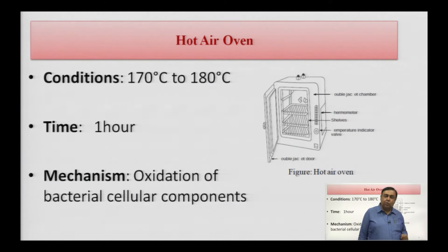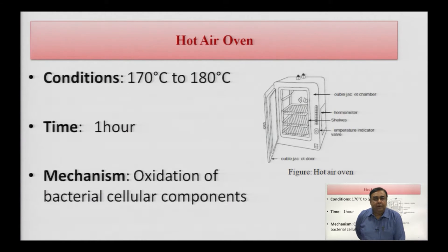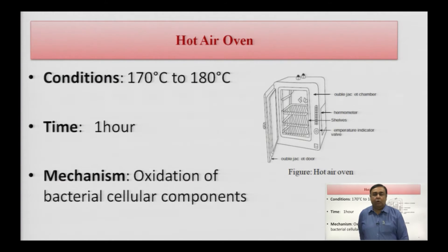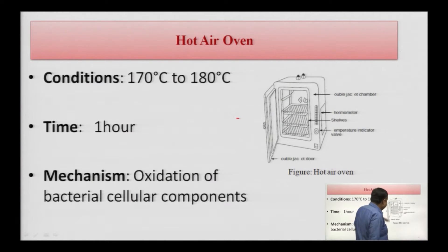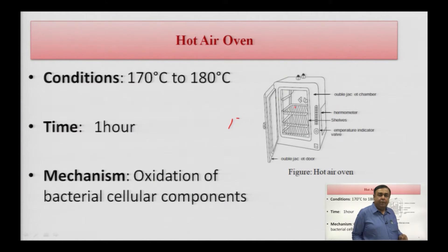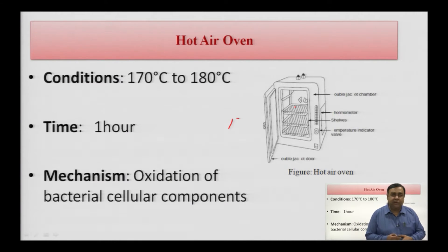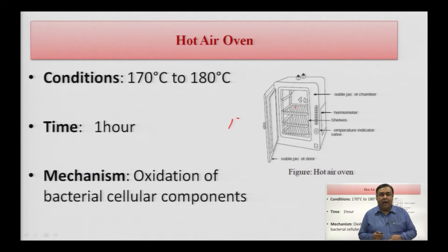The instrument commonly used in industries for dry heat sterilization is the hot air oven. The hot air oven is basically a double-jacketed machine with a large number of trays. You place the material on the tray, close the outer door, and a thermometer inside records the temperature. The temperature is maintained at 170 to 180 degrees Celsius for a minimum of one hour.